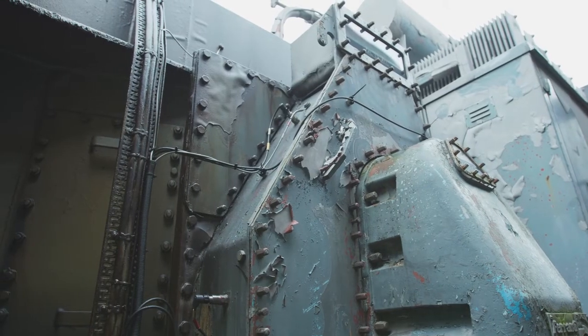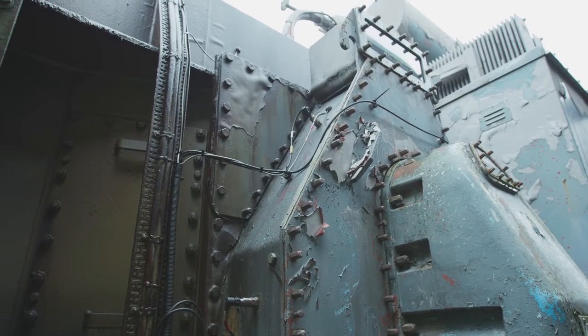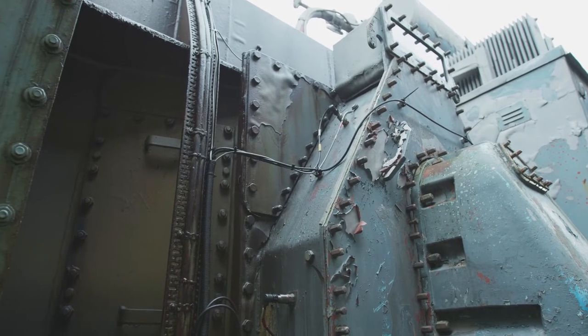What we found on the initial process was that although we got a good result for short term, as the unit was put back into use, those impurities came out of the core and the oil quality degenerated again. So by doing this two-stage process, it produces a much longer lasting effect and gives us a better impact on transformer life. One of the parts of the transformer that's most prone to failure is the tap changer, because that's the part at which you have the mechanical movement.